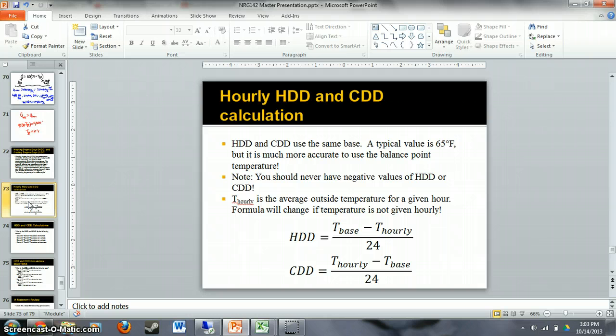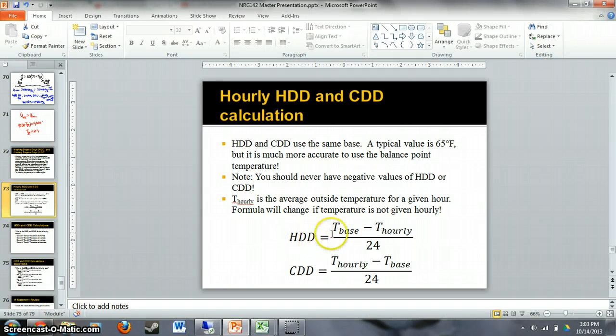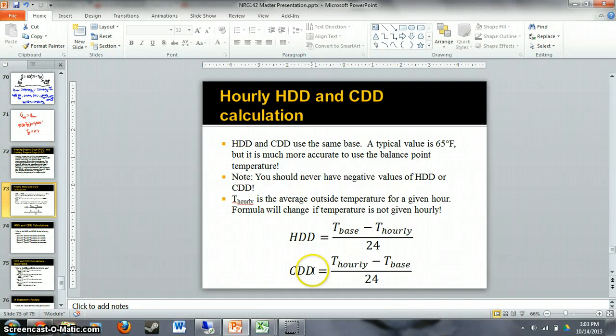T_hourly is the average outside temperature for a given hour. We'll see later how the formula changes if temperature is not given hourly. If temperature is given hourly, heating degree days equals T_base minus T_hourly divided by 24. For cooling degree days, it's T_hourly minus T_base, still divided by 24.